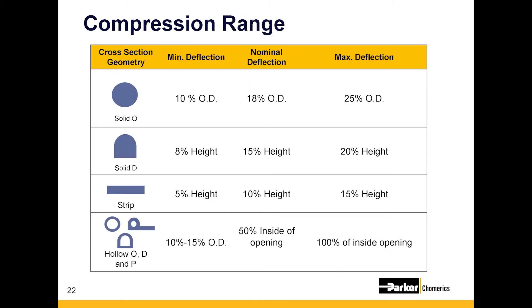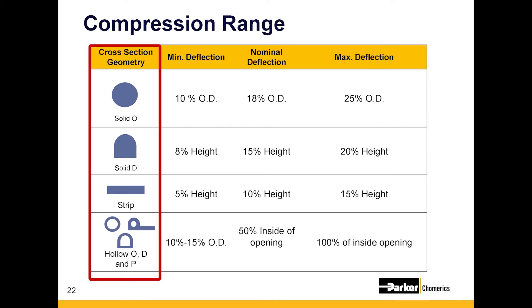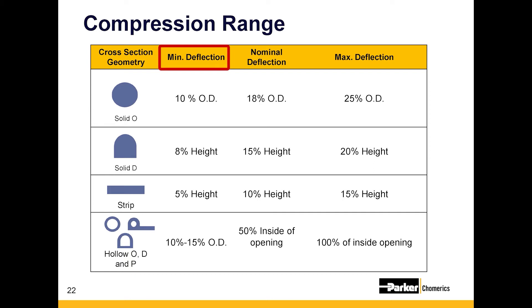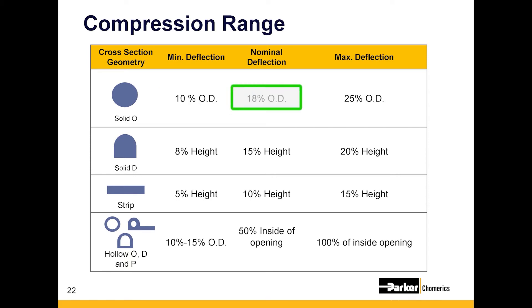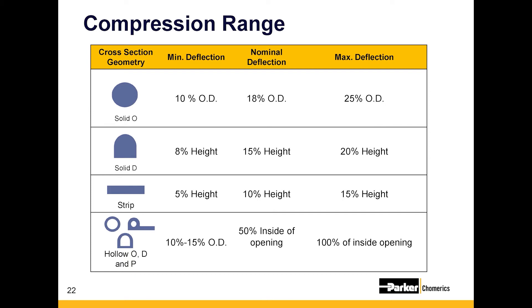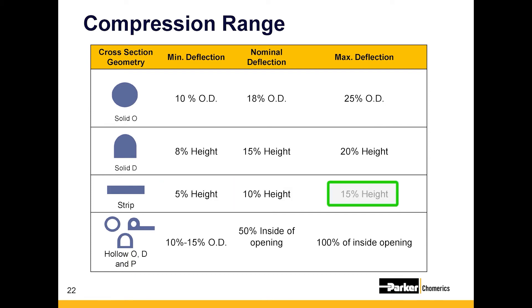Compression forces are something important to look at from the beginning — a lot of common mistakes are made around housing design. Looking at the different profile types on the chart, there's a minimum, nominal, and maximum deflection range. For a solid-O: 10% minimum, 18% nominal, and 25% maximum. For a flat strip: 5% minimum, 10% nominal, and 15% maximum of the height.